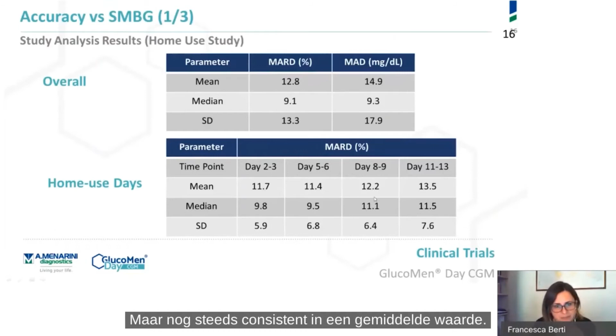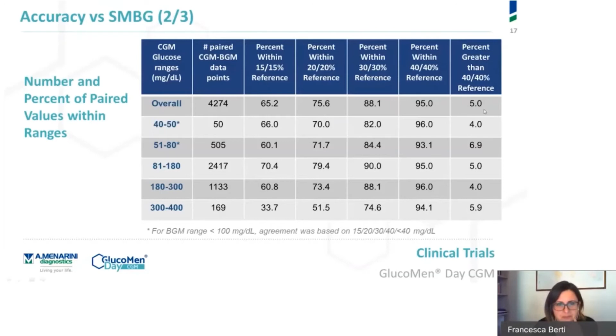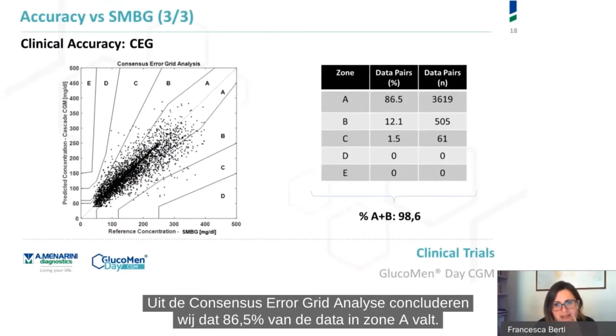The more detailed performance assessment of the bias versus the BGM reference is shown in this table, and we can see that 65.2% of the data pairs show a bias within 15 milligrams per deciliter or 15% of the reference value, 75.6% fall within 20 milligrams or 20% of the reference value, and only 5% of the results showed a bias higher than 40 milligrams or 40% of the reference value. From the CEG analysis, we can see that 86.5% of data fall in zone A, and that 98.7% of the data fall in the combined A and B zones.